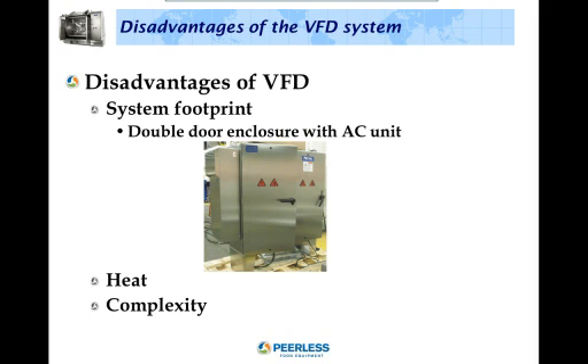Adjusting the speed of a mixer during the mix cycle may also allow you to decrease the mix time while still introducing the same amount of energy into the mix. The variable frequency drive provides improved working conditions with less noise and vibration as the machine starts up and changes speed. This also impacts the maintenance requirements. A further benefit is the elimination of the power surge that can occur on a two-speed mixer when it is started or changes speeds. This can cause a drop in factory voltage and reduce torque on the mixer motor that may lead to stalling. Disadvantages of the VFD.